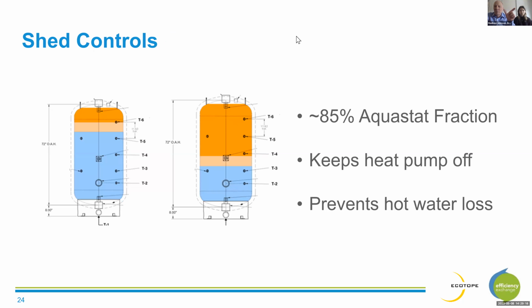And then during that shed period, when we would rather the heat pump doesn't turn on, we're using an aquastat way at the top of the tank, so that it allows the whole bottom of the tank to get drained down. We don't let it drain all the way because we don't want people to run out of hot water. So we turn it on if that cold water level gets up towards about 85% of the tank. And then we turn it on to recover down to about that 40% level, and then we'll let it come back on again if it needs to cycle during that shed time.